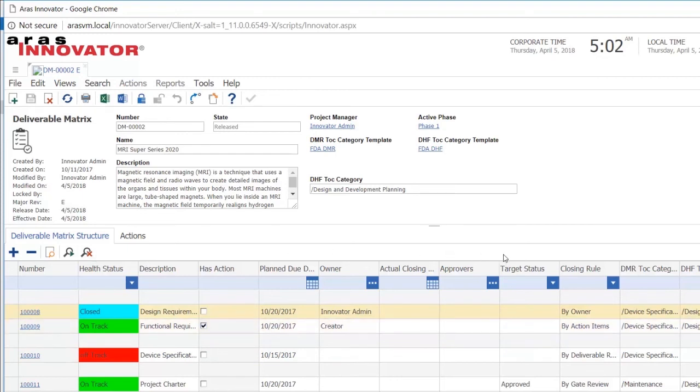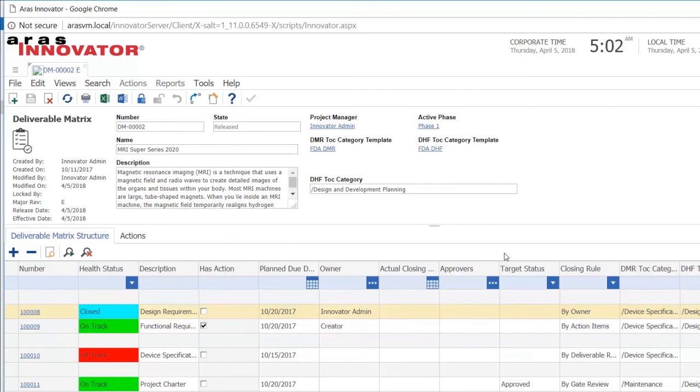What we can also see is that we can indicate where in our DHF and DMR do we want this deliverable, the actual documentation, to be placed. Because we also have templates for DHF and DMR and we relate the templates to the actual deliverable matrix. So when we create the deliverable matrix, we not only create the list of deliverables, the deliverables itself, but we also create the DMR and DHF automatically. And each of the documentation in here or deliverables will automatically be placed in the correct section of the structures as we have decided in the template.